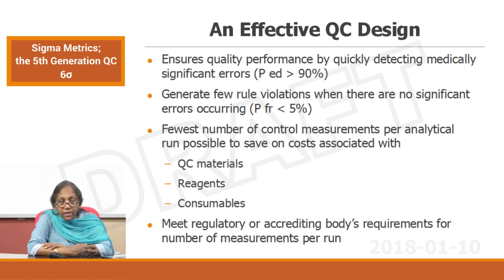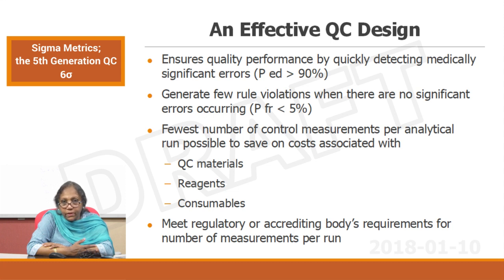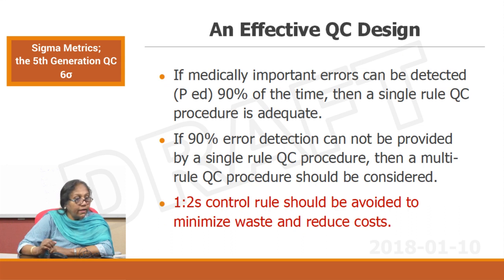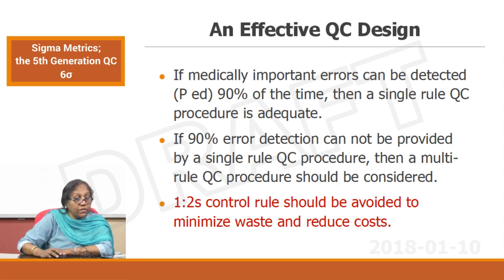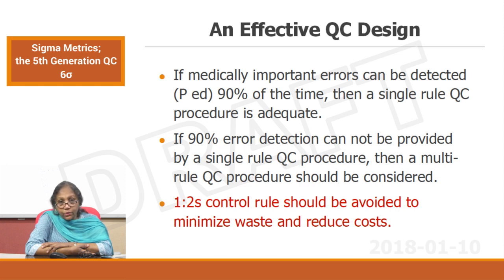That is also important because NABL, if it is asking for two levels of control for a certain number of patients, that is a regulatory requirement if you are looking for NABL accreditation. A very high sigma — like 6 sigma — technically will not need you to do more than one level of control, but if NABL regulations require two levels, then you have to comply with that. An effective QC design will have medically important errors detected more than 90 percent of the times, and if 90 percent error detection cannot be provided by a single QC procedure, then a multi QC procedure should be used. Also, the 1-2S rule should be avoided as a rejection rule to minimize waste and reduce cost — unless you have only one level of QC in your laboratory.